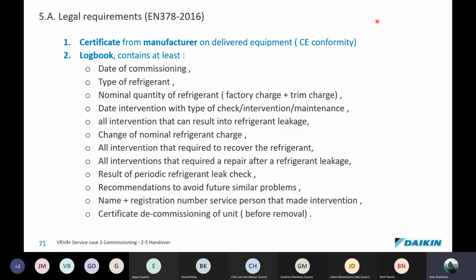On that form, we give a date, type of refrigerant, nominal quantity of refrigerant, and quite a bit of other information as well. But this is not a legal document, it's our commissioning report to the company who has done the installation. You need to have a look at your local legislation, and if you're required to do refrigerant leakage checks, then those should be adhered to as well. And all intervention that requires recovering refrigerant should also be documented and left on site.